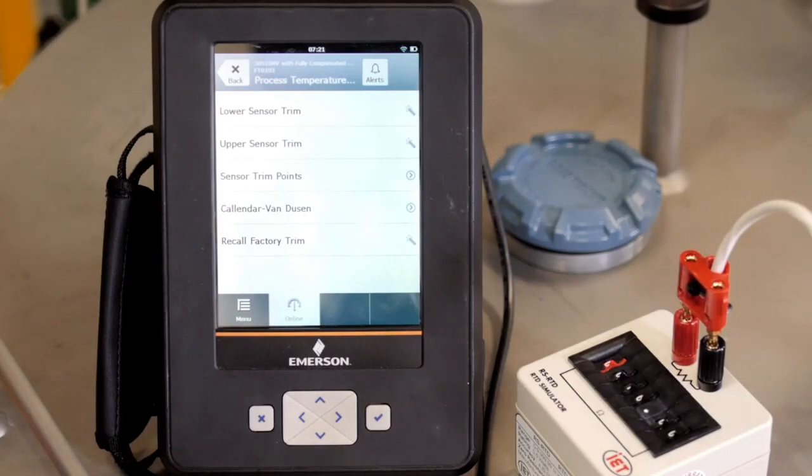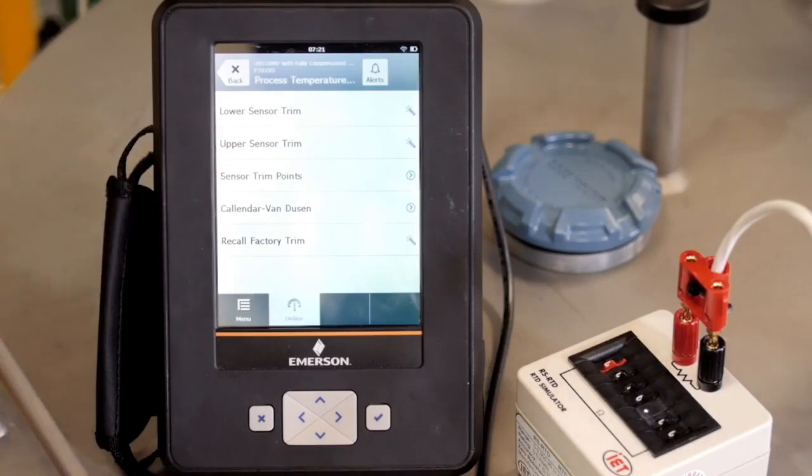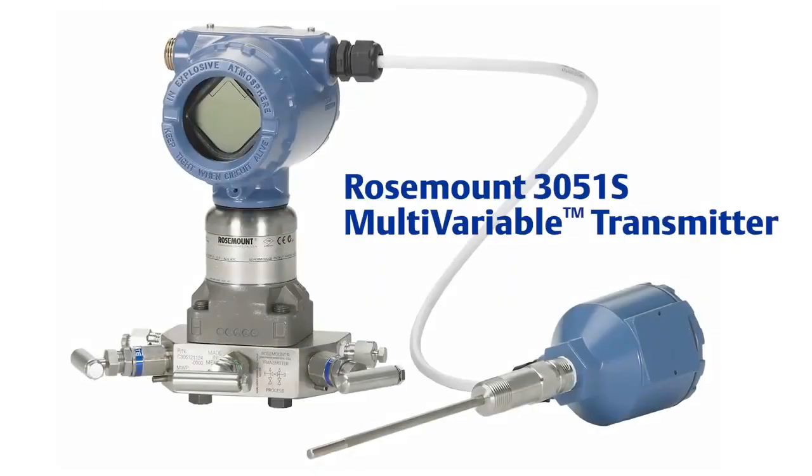From here we can follow the Trex guided wizards for the lower sensor trim and upper sensor trim options. Keep in mind this process calibrates the temperature input on the transmitter and not the RTD itself. Once the lower and upper trims have been successfully performed, the calibration of all three sensors is complete.